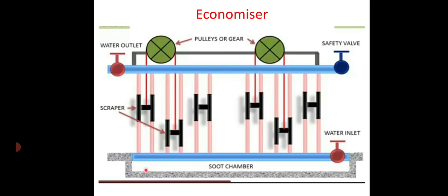The economizer is built up of transverse sections. Each section consists of generally 6 or 8 vertical tubes. These tubes are joined in a horizontal pipe or box at the top and bottom respectively. The top boxes of different sections are connected to one pipe, while the bottom boxes are connected to another pipe. These pipes are outside the brickwork enclosing the economizer.